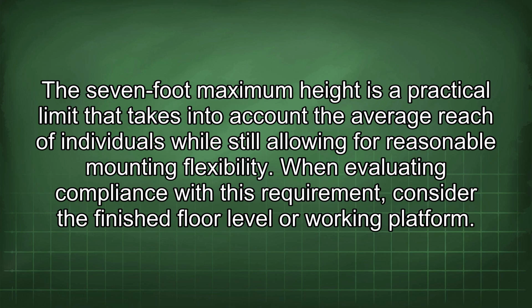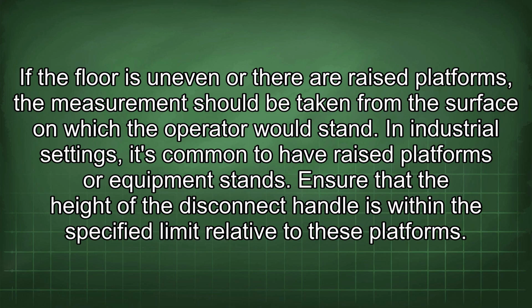When evaluating compliance with this requirement, consider the finished floor level or working platform. If the floor is uneven or there are raised platforms, the measurement should be taken from the surface on which the operator would stand. In industrial settings, it's common to have raised platforms or equipment stands. Ensure that the height of the disconnect handle is within the specified limit relative to these platforms.